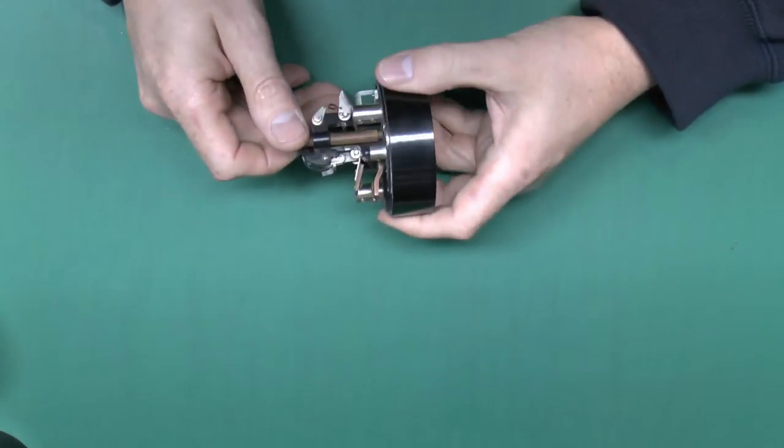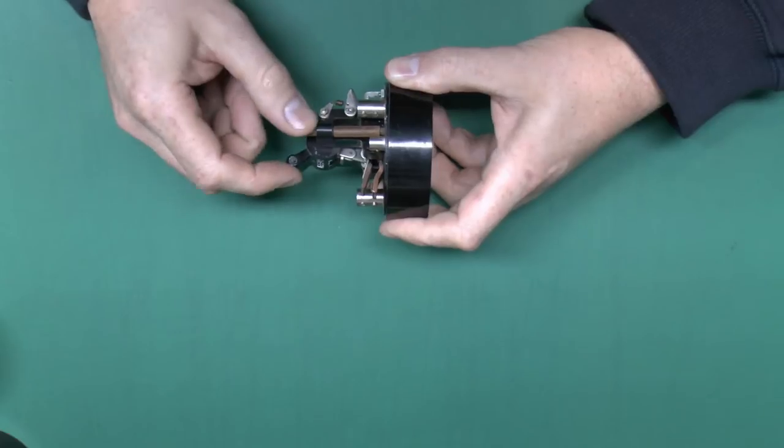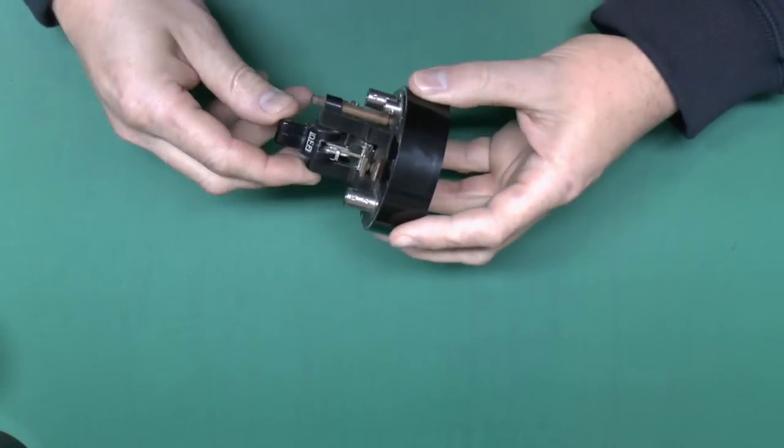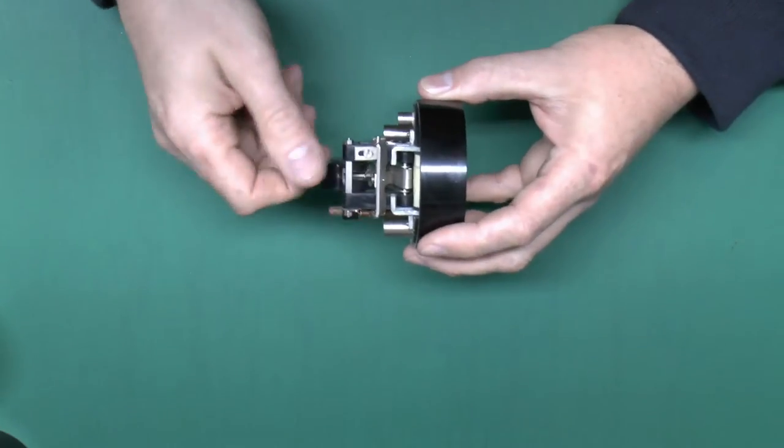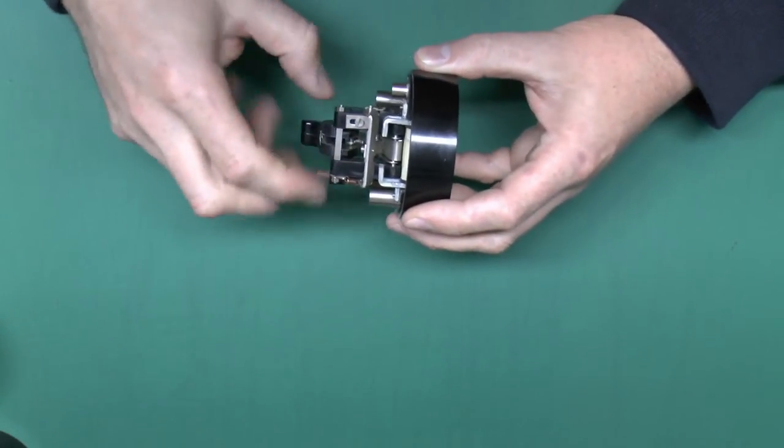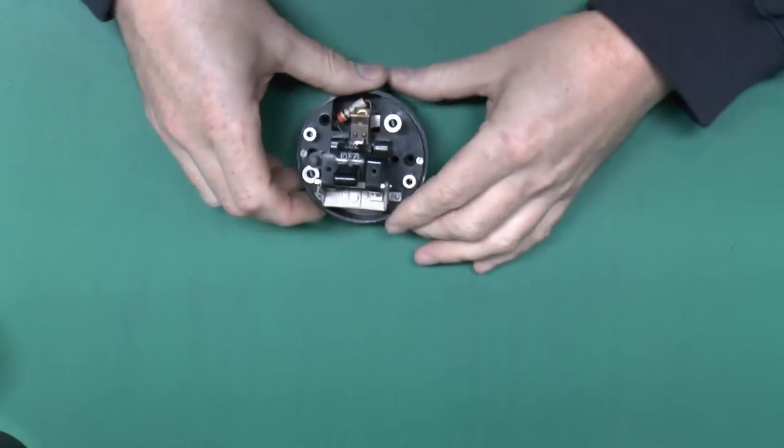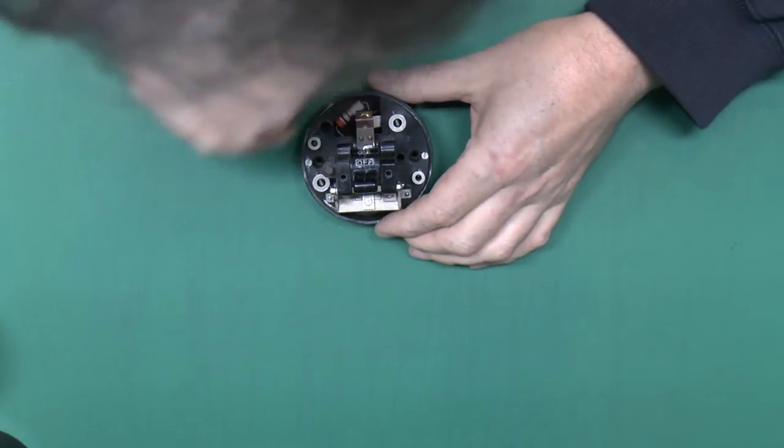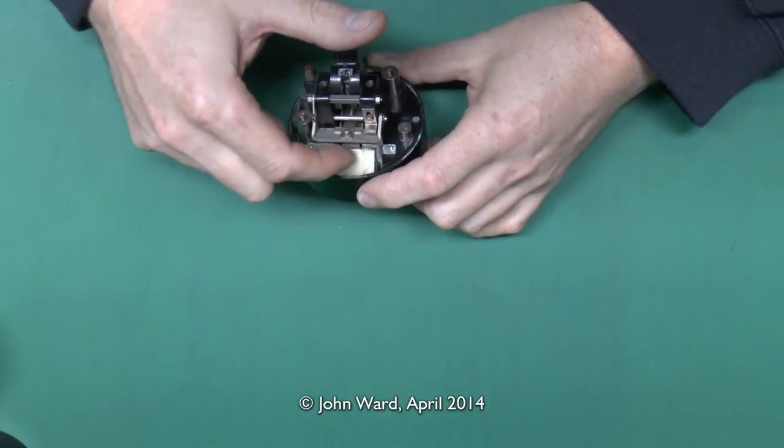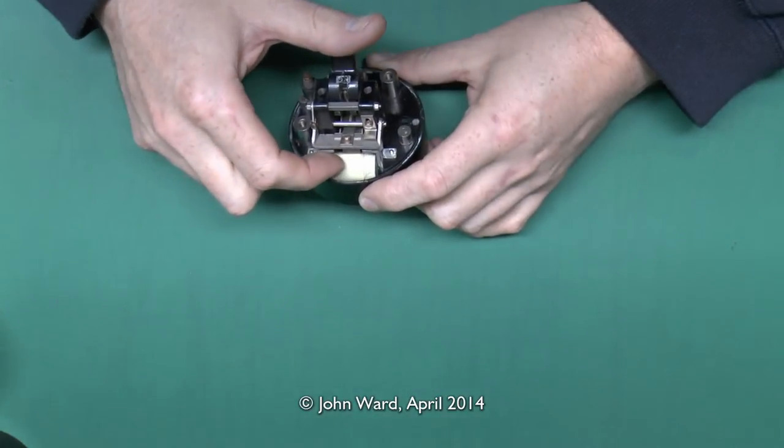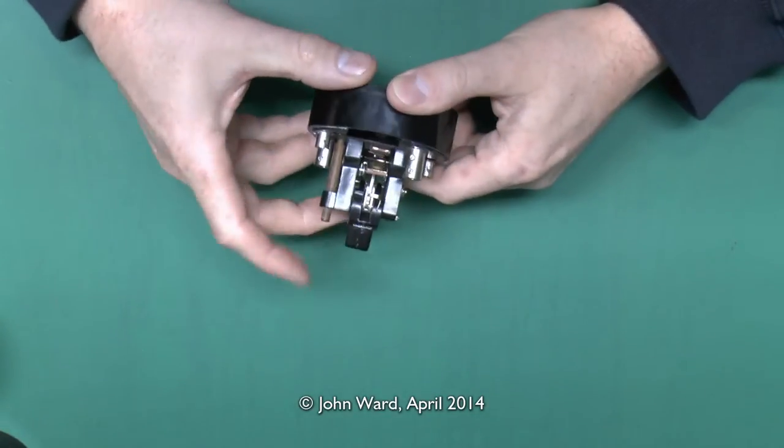Now this is only a single pole device and we can see the main contact there. So it just presses together like that and then when it trips off it just springs apart. One interesting aspect of these is they have to be operated in the correct vertical position because if you put it this way up you can't actually reset the thing because it relies on gravity to move the various parts into the correct position. So main switch on the front there just the contact. There's a resistor in the back there and at the bottom here you can see there's a coil.